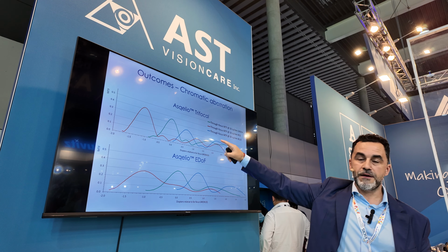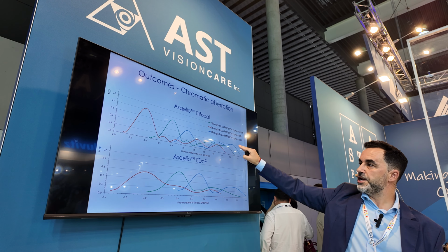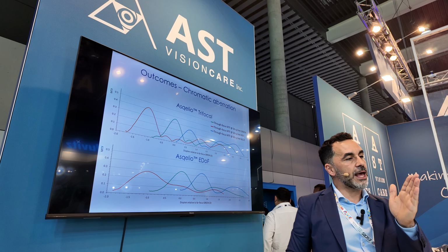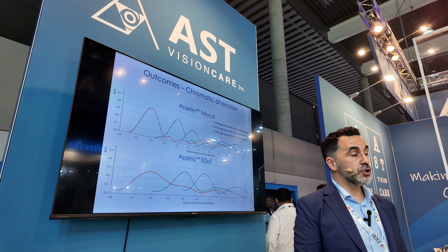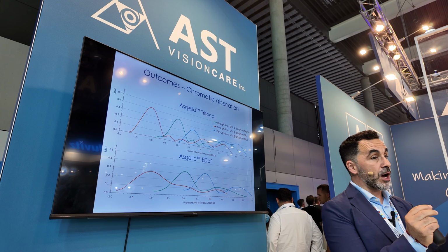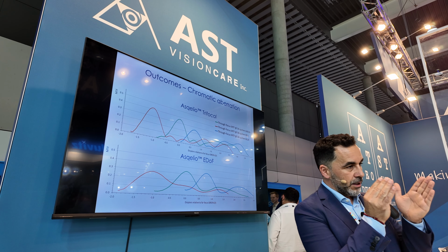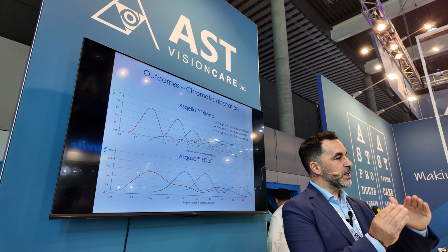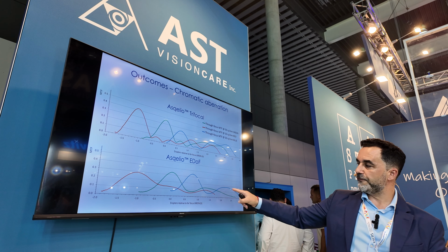Now in the trifocal we can see more clearly the intermediate and near different foci. We can see that the drop in MTF from the intermediate and near is not huge, and that comes from the various technologies applied to the design of the trifocal IOL, which means that the diffractive pattern they use creates a depth of focus-like shape within the MTF curve from the intermediate to the near. So there's barely a drop in the MTF response at that distance, and we can see that for the near one.